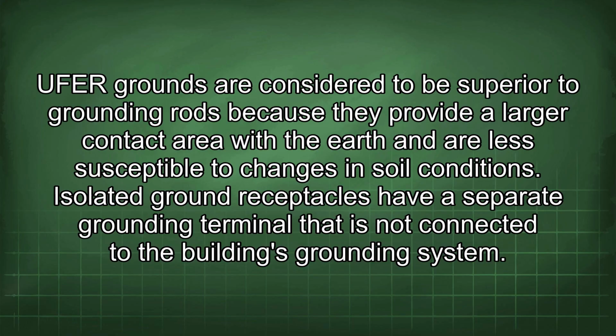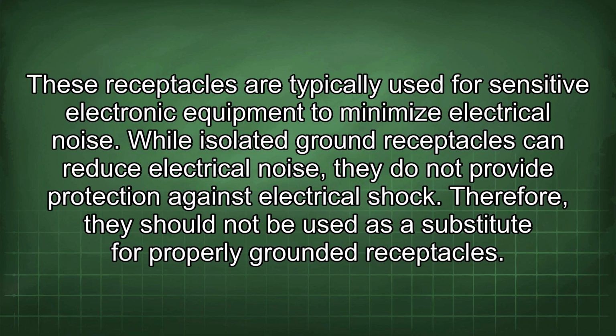Isolated ground receptacles have a separate grounding terminal that is not connected to the building's grounding system. These receptacles are typically used for sensitive electronic equipment to minimize electrical noise. While isolated ground receptacles can reduce electrical noise, they do not provide protection against electrical shock. Therefore, they should not be used as a substitute for properly grounded receptacles.